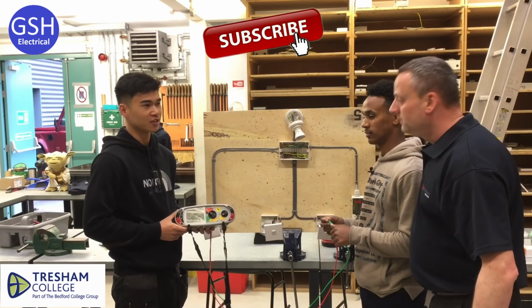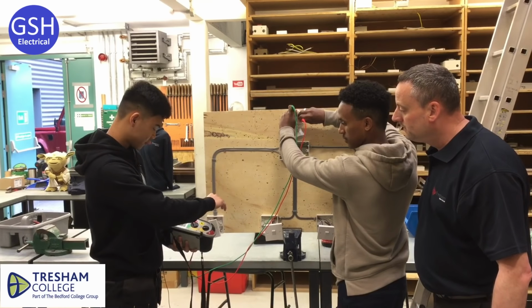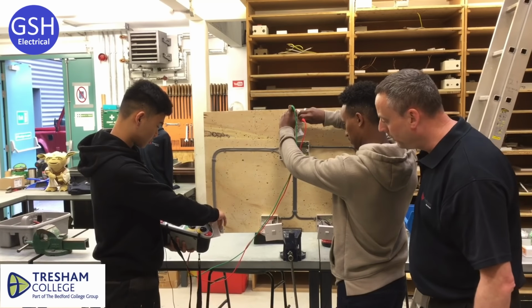Are we zeroed out? Yep. Okay, so we're going to probe on to which conductors? CPC and then line switch. Yeah, switch line and CPC. Now the circuit's on, it's currently on, and we've got a reading, Joe, of? It's 0.18.